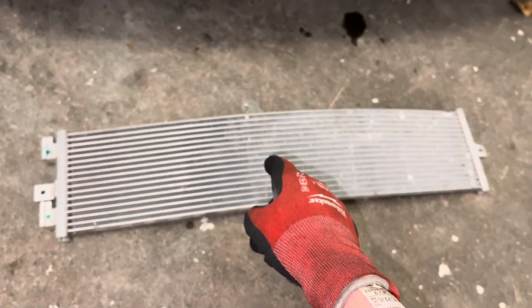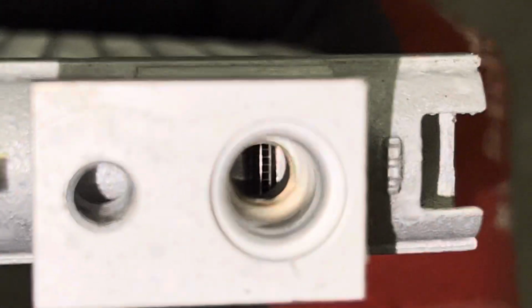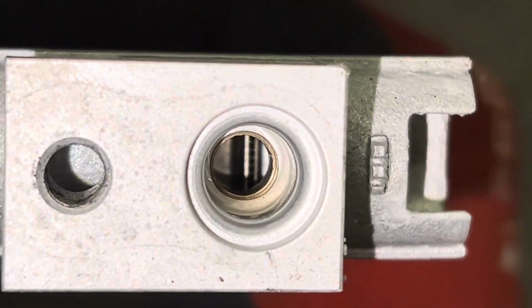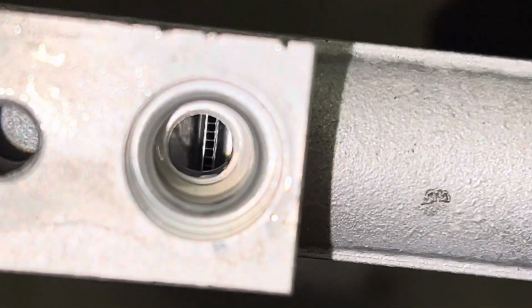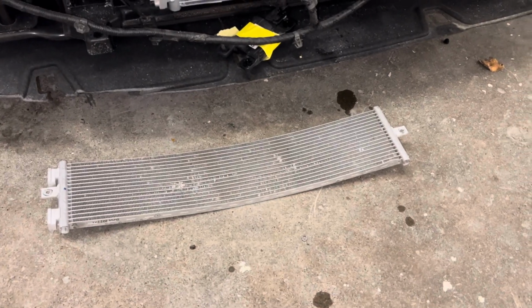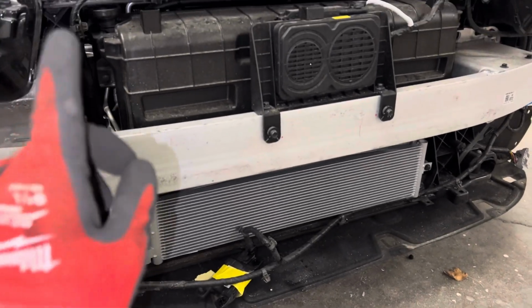But let's get back to this. Take a look. Look in here, do you see those openings? Let's see if I can zoom in there. Now let's see if the camera wants to focus. You see those openings? Those are exactly the same size. This is a subcooled circuit. If you know this is a subcooling circuit, now you go, well, where's the condensing circuit? The condensing circuit is in the glycol water loop.